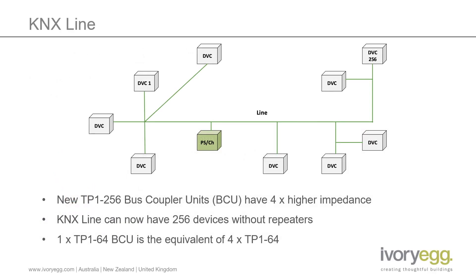When a telegram is sent on the bus, the signal is impacted by each device on the line, which eventually impacts the readability of the telegram. This is the reason we have a maximum number of devices per segment to ensure the correct operation of the bus at all times.